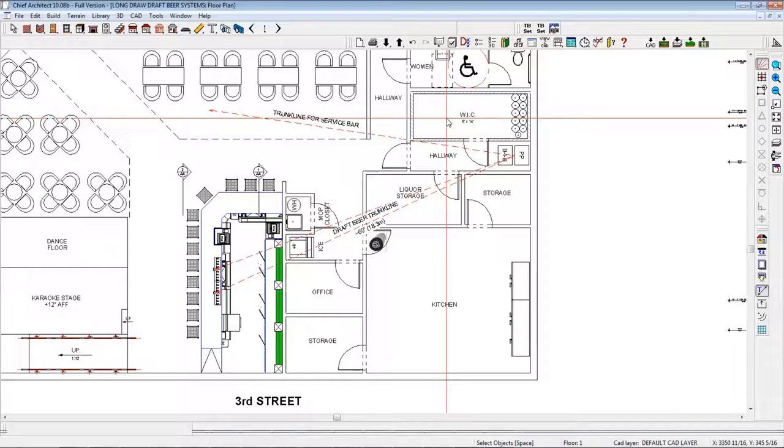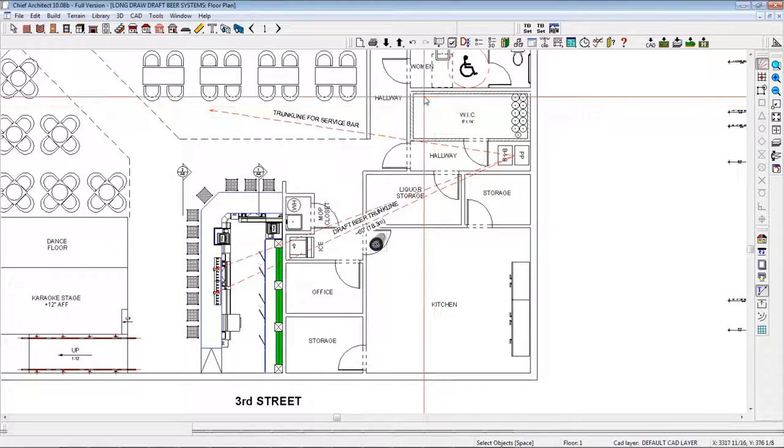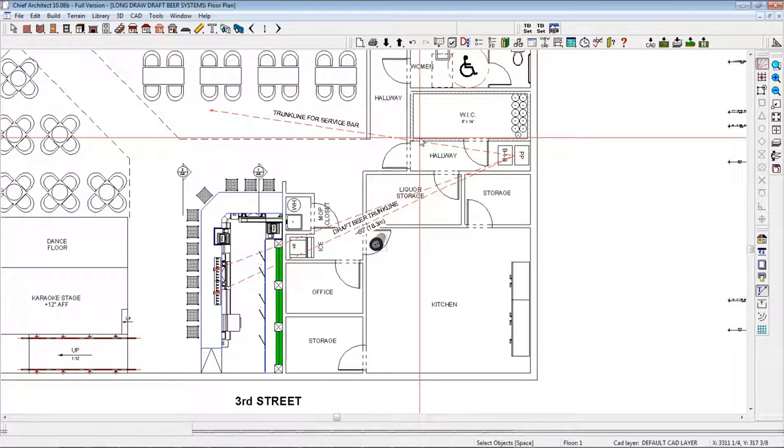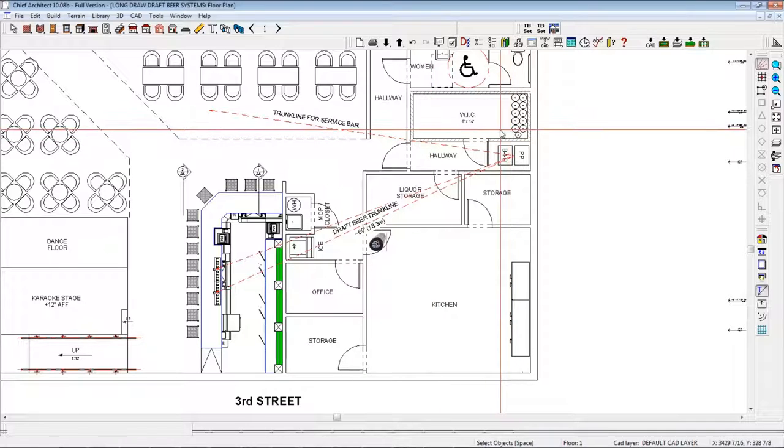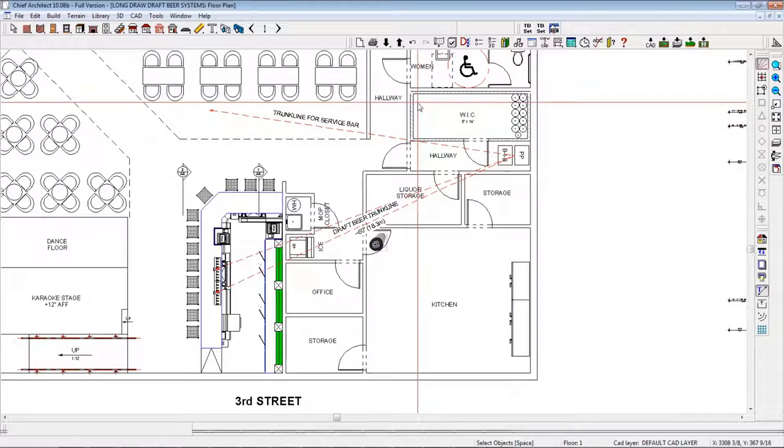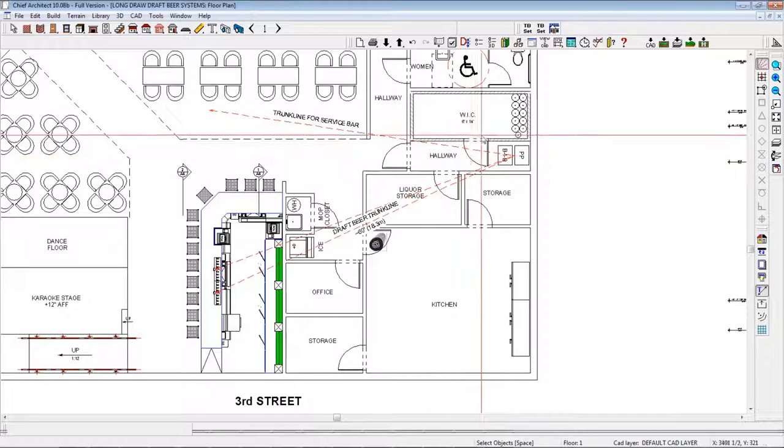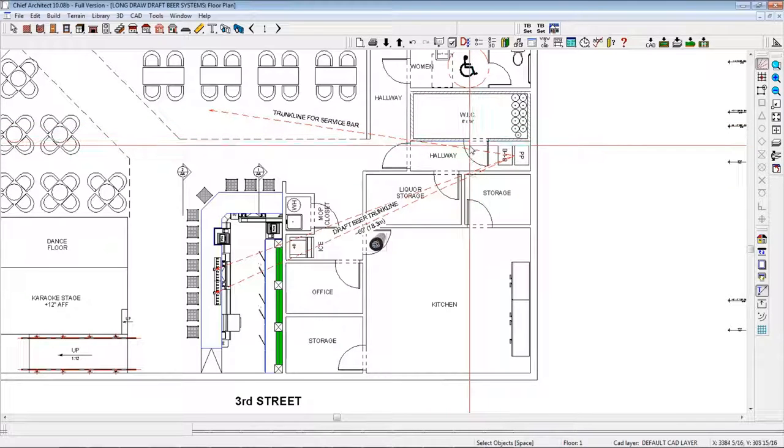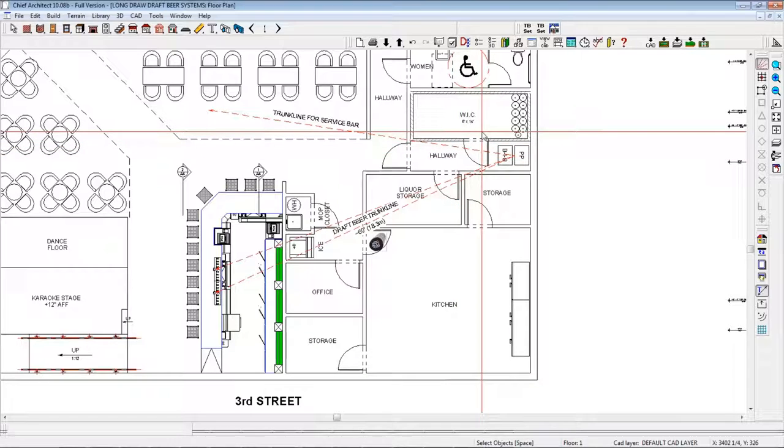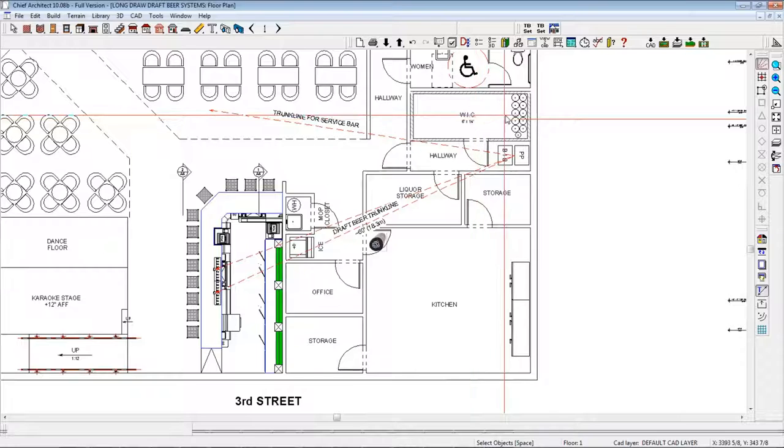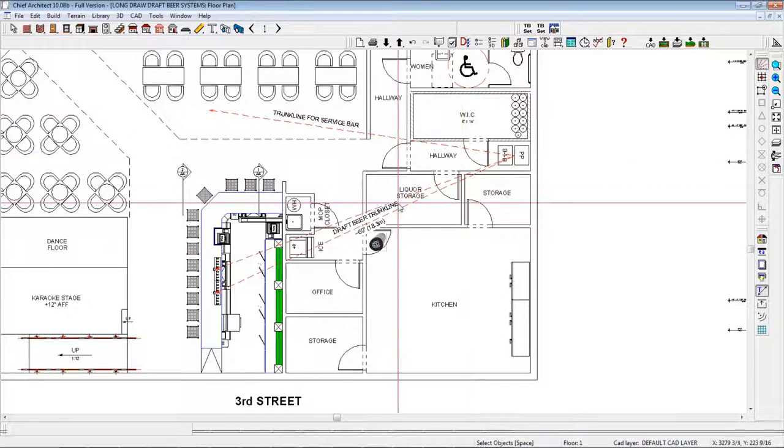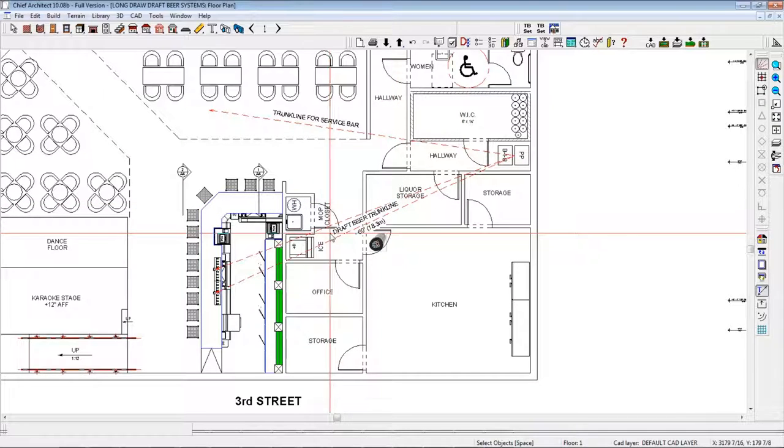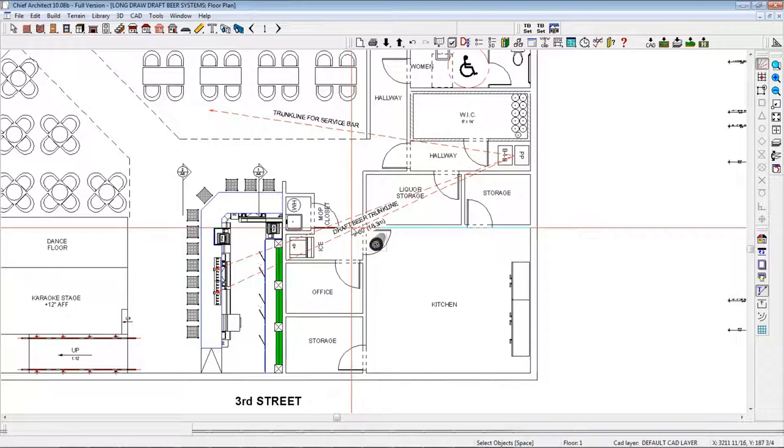So therefore, really what you should do is dedicate a walk-in cooler exclusively for your draft beer, so that you don't make the mistake of putting your case beer in there and having people go in and out of this walk-in cooler all day or all night long, whereby maintaining that ideal temperature within the cooler becomes sort of a pipe dream, because you really need to keep this cooler in the 36 to 38 degree Fahrenheit range or it just simply isn't going to perform. And then your glycol system really is suffering for it and your investment really is sort of wasted.